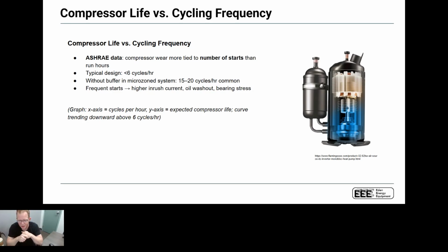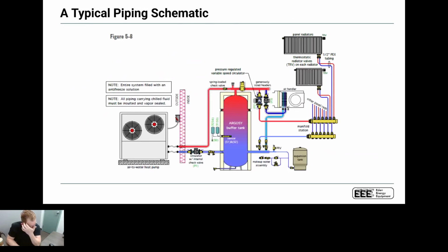The buffer tank is dictated by the design. What is the load on the degree day? What is the load on non-degree day? What does the house look like? Is it an air handler? Is it radiant floor? Is it a low temperature convector like I showed you? There's so many options that we need to make sure we're aware of, but just understand with an air to water heat pump, it's easy in my opinion, but if you miss a step, you can end up with problems that can be quite expensive that you don't want to deal with.